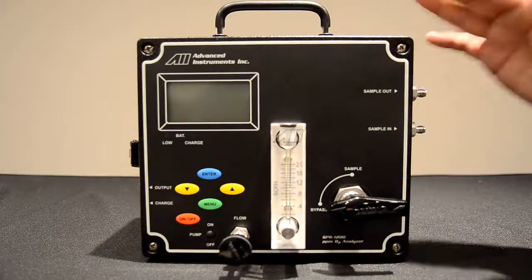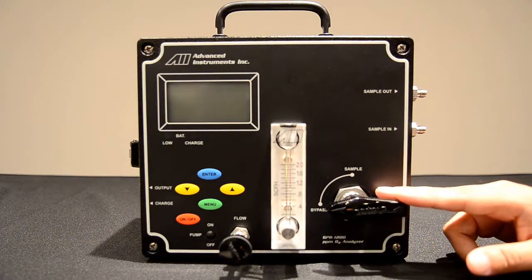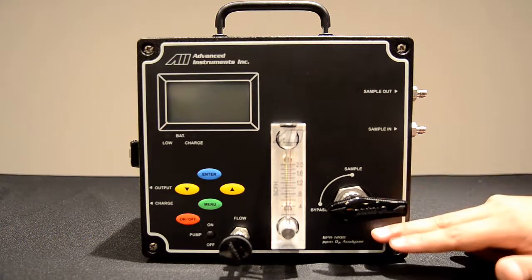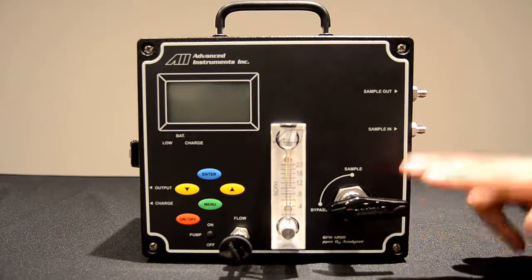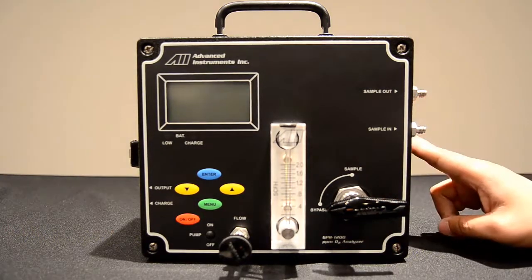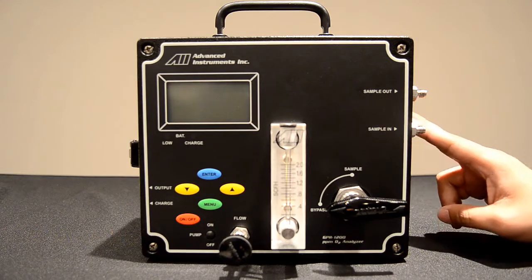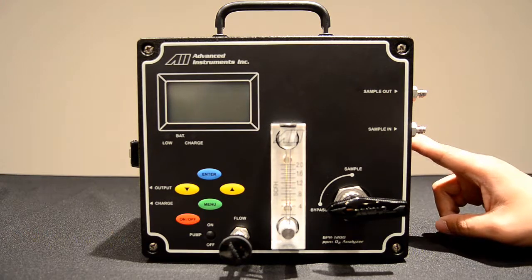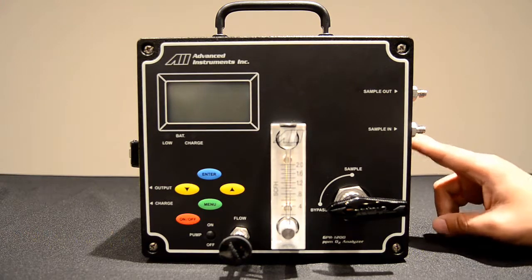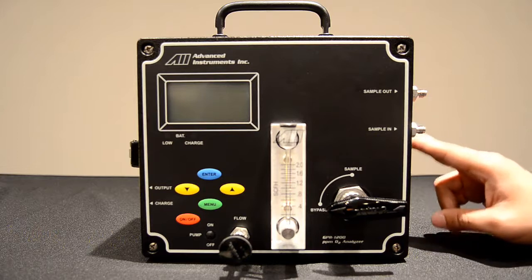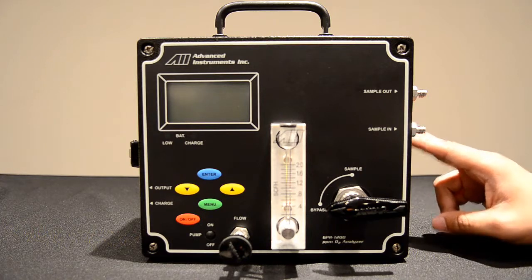A key feature of this analyzer is the integral bypass valve. Currently the analyzer is in bypass, ensuring that the sensor installed during shipment is preserved from ambient air. The sensor is sealed both on the inlet and the outlet preventing any gases from exposing the sensor.